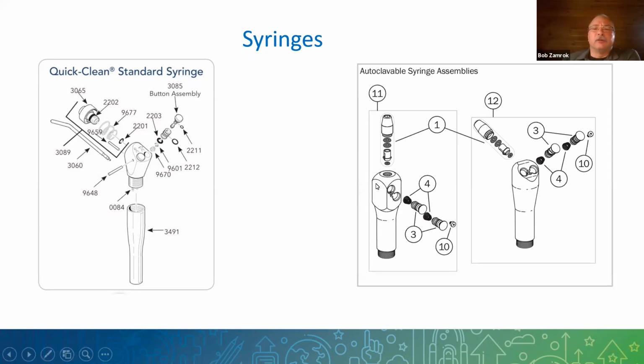If you have water leaking out, a lot of times you can just pull the valve out, clean it, and get whatever debris is in there out. Put it back in with a little fresh lube on it, and the problem's solved. Or if it sticks and you've got water constantly dripping out of your syringe tip, pull that water valve out, clean it, and pop it back in, and that'll go fairly well for you.